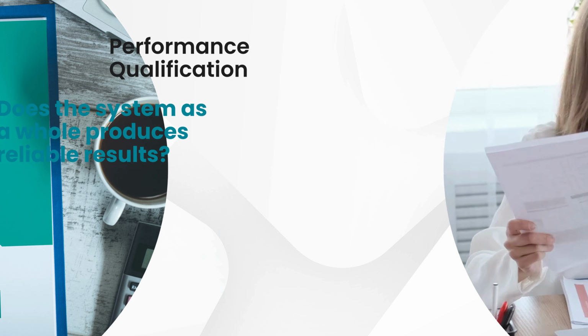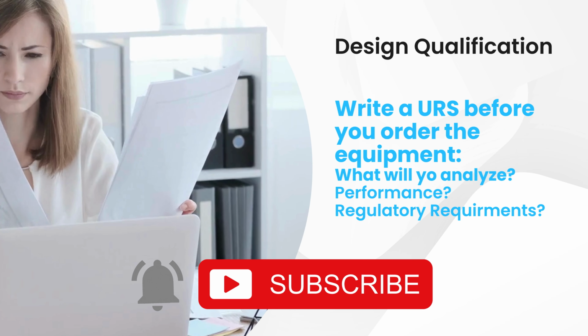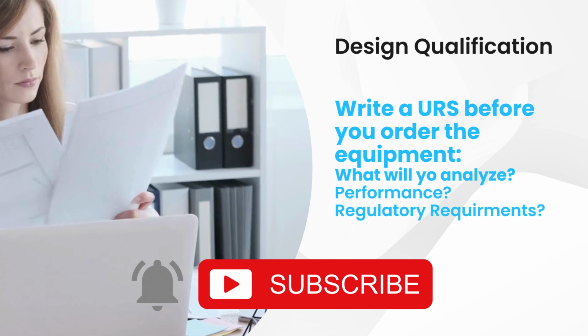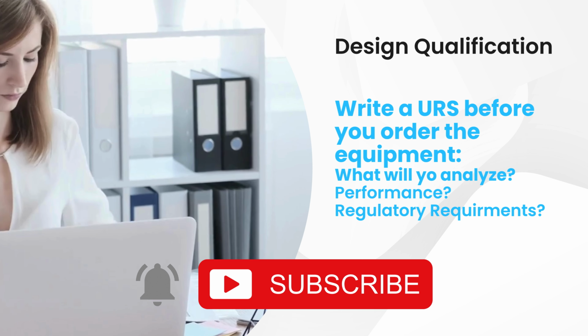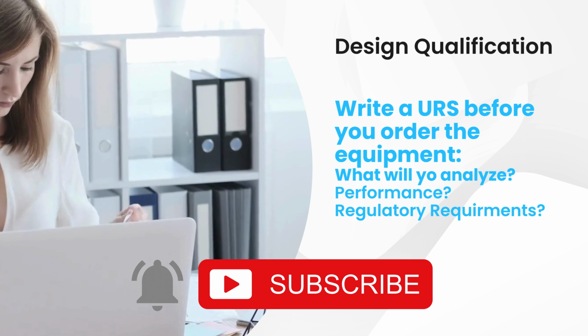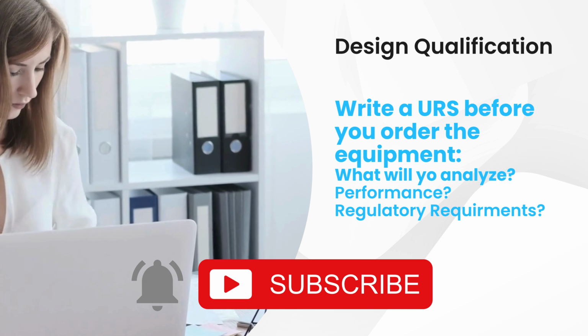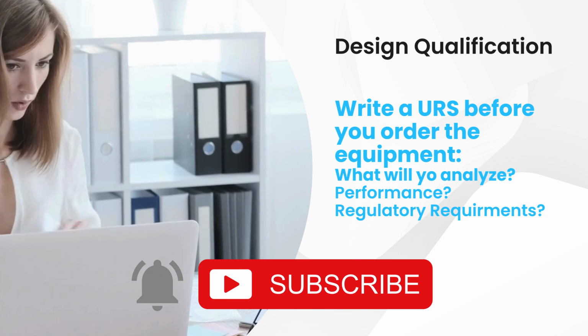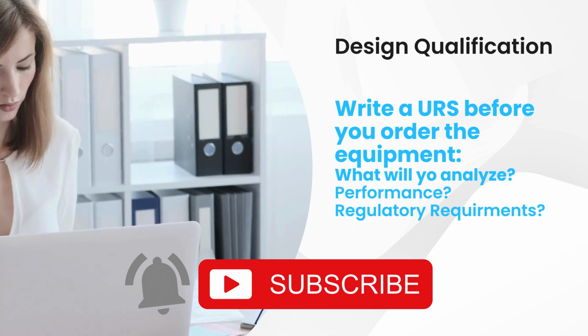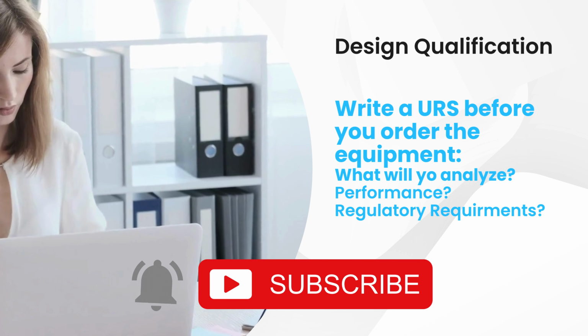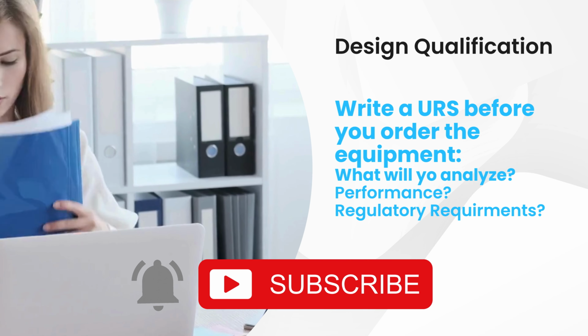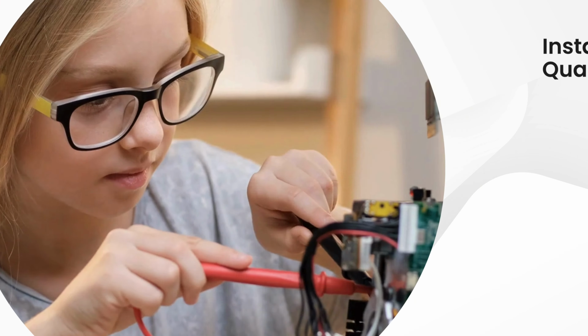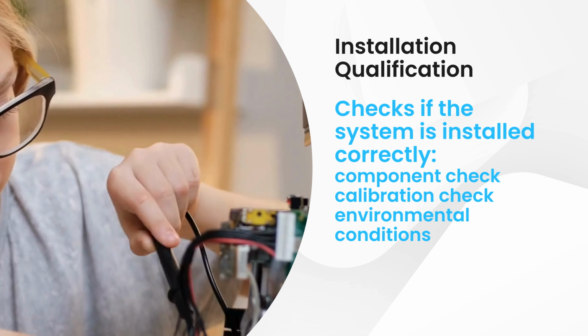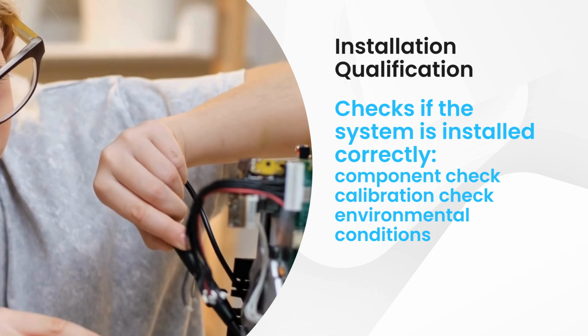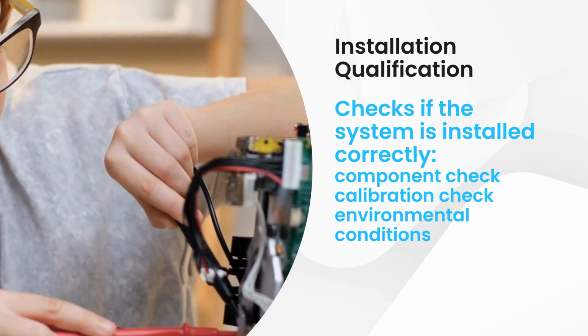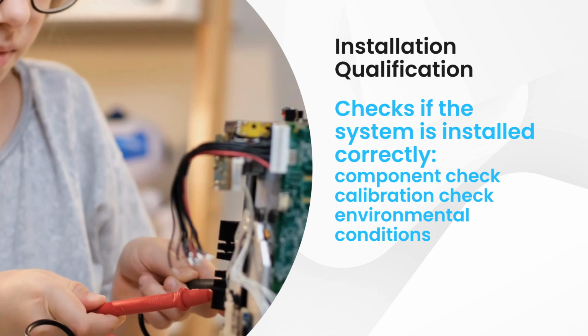Let's look at each stage in more detail. Design qualification. Before purchasing an HPLC, define your needs. What types of samples will you analyze? What separation performance do you require? Does the instrument meet relevant regulatory standards? DQ is usually performed by the user, sometimes in collaboration with the vendor. Installation qualification. When the HPLC arrives, follow the manufacturer's instructions meticulously. Document everything: serial numbers, installation dates, and any environmental conditions. Verify that all components are correctly installed and that the system is ready for operation.